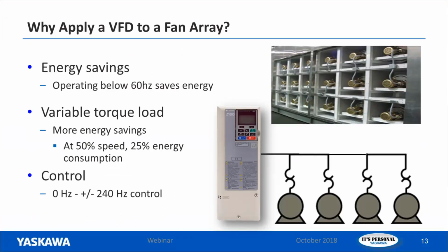So why would we apply a VFD to a fan array? There are three main reasons, and really they're all closely related. First would be energy savings. As soon as you have the ability to run a motor below 60 hertz, you have the ability to save energy and, of course, save money.